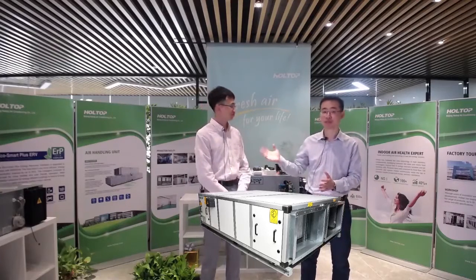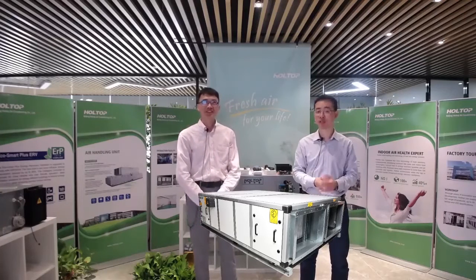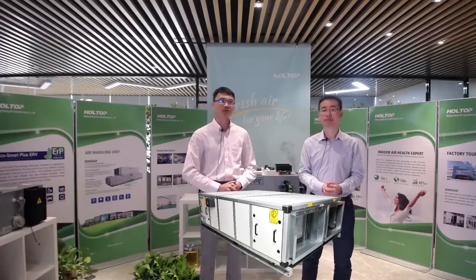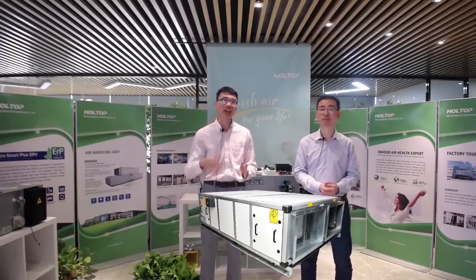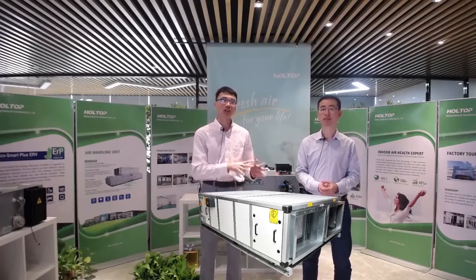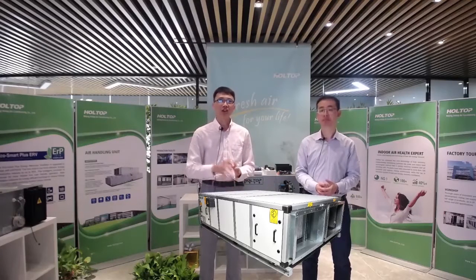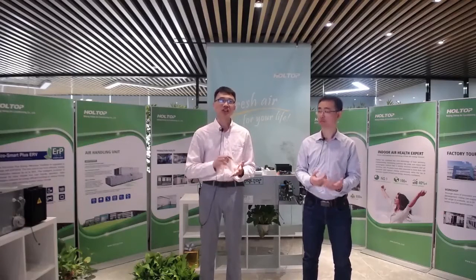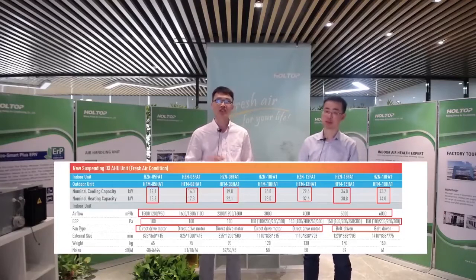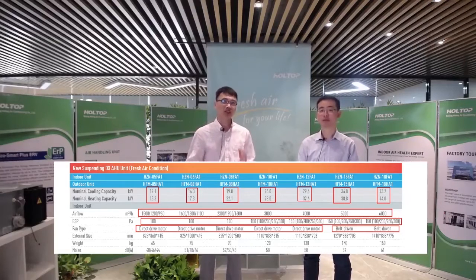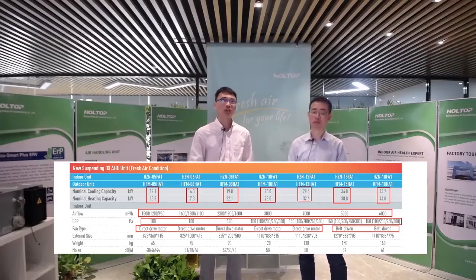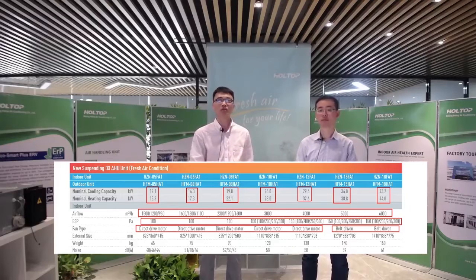Okay, so Ken, please introduce the 100% fresh air unit. Yes, so we have another type especially for fresh air handling, and we call it the 100% fresh air type. And for the air on coil, the outdoor temperature is designed as 35 centigrade, and the air off coil temperature is as low as 23 centigrade. Yeah. And we have a lot of cooling capacity options. Our cooling capacity could be from 12 kilowatts to 43 kilowatts. And all the units are heat pump type.